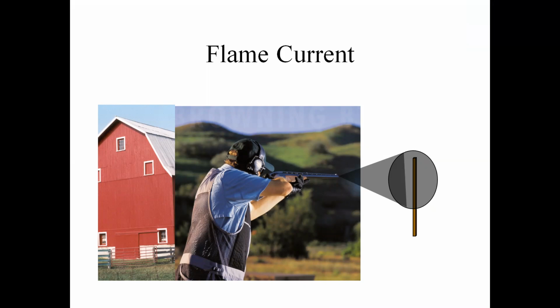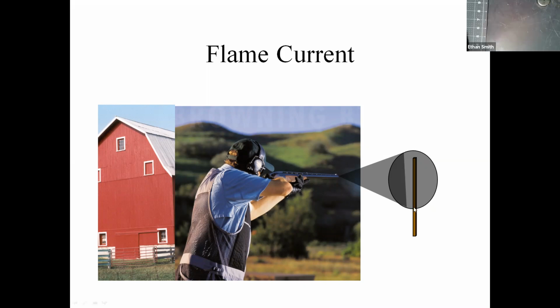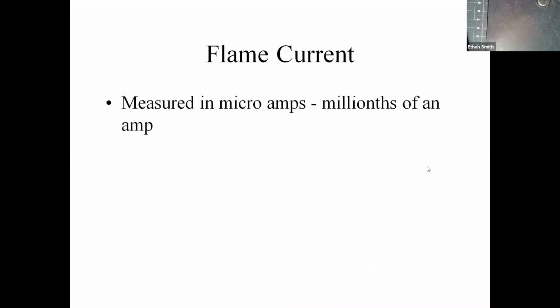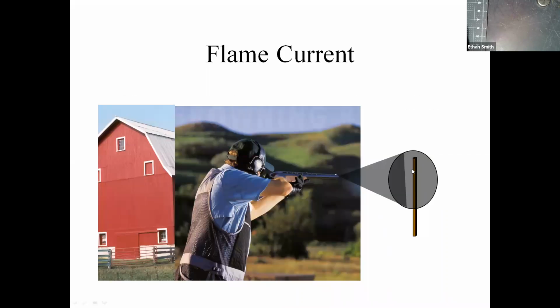The lower third. Yeah, it's just going to get pellets down here where that outer ring. Okay, so what we do with flame sensors is, you'll notice flame sensors are typically positioned kind of over in this section. So the flame sensor, if we move that over here, is actually going to pick up 2 points on that circle. Okay, and what we do is we pass AC voltage up this flame sensor, and it rectifies to DC through the flame and goes to ground at the face of the burner.